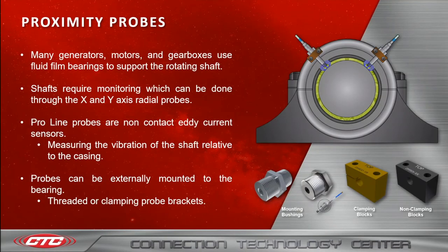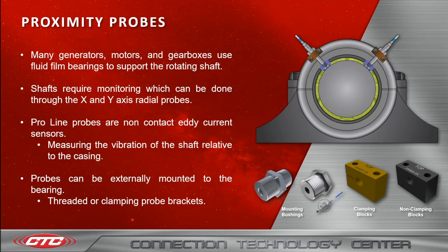That leads us into proximity probes. Many generators, motors, and gearboxes use a fluid film bearing to support the rotating shaft. Shafts require monitoring, which can be done through the X and Y axis radial probes. You can see in the picture to the right that the proximity probes are mounted on the bearing.